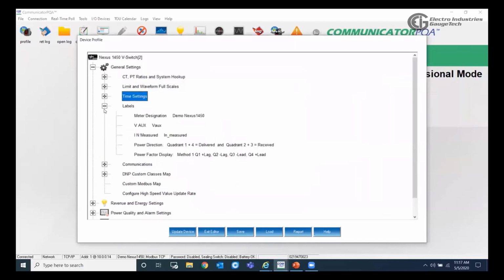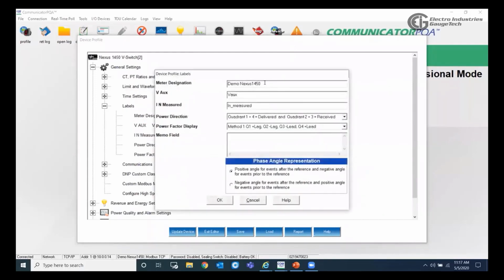The next section is the labels. Under the labels, this is where we can give the name for the meter. As you can see, we have the meter designation, and this was the name we saw when we connected with the meter, so we can give a different name from here. We can also give a label for the voltage auxiliary and for the neutral current. The power direction is where we can change the labels for the energy. By default, quadrant 1 plus 4 is considered the delivered, and 2 and 3 is the received. We can choose the reverse type, and this is all about labeling.